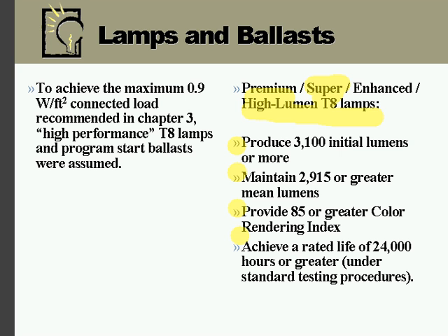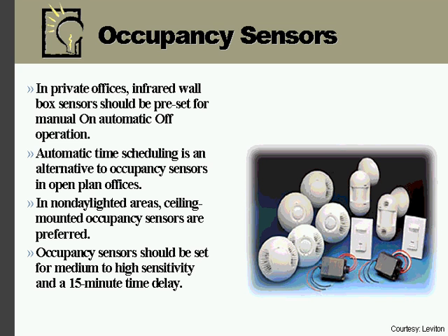So going back to the recommendations, the recommendation is just 0.9 watts per square foot. High performance is what we use to model it, and it's one way to meet the recommendation.